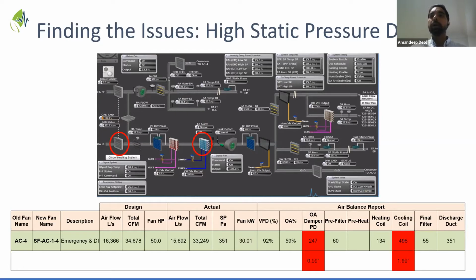And the majority of the time, with things like these, when you expect the outside air damper pressure drop to be around 0.1 and you're seeing 1 inch, it tells you that there is an issue, whether it's a stuck damper, or whether the louver needs to be cleaned, or the mesh needs to be cleaned.